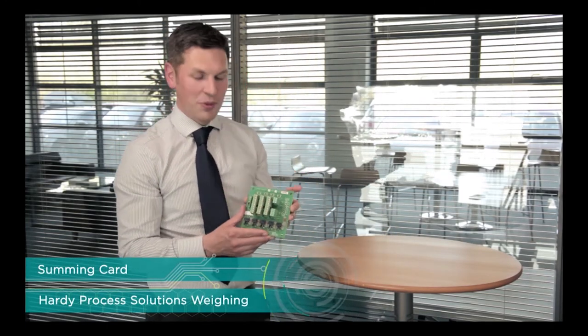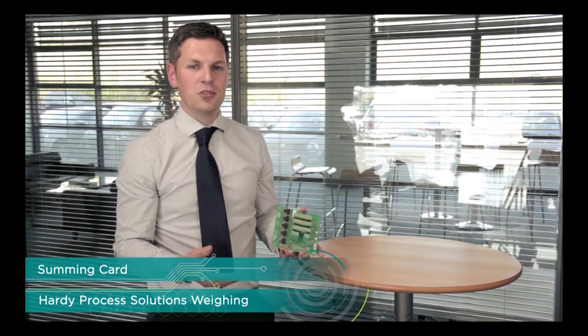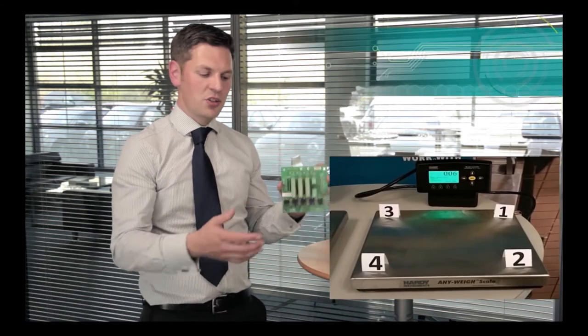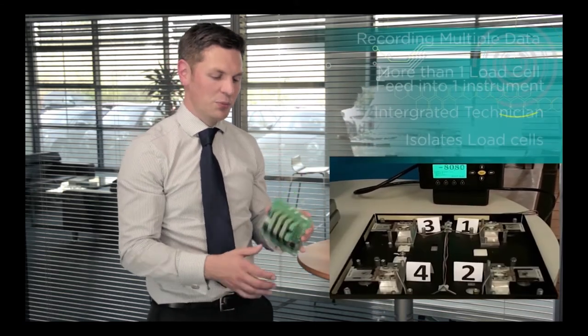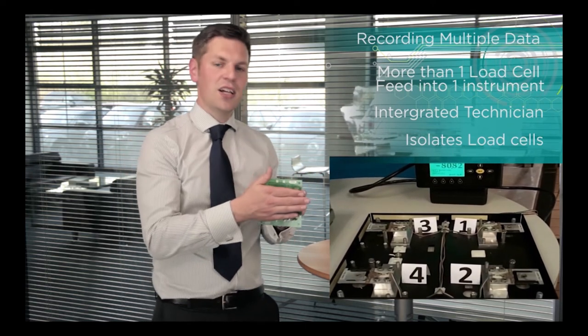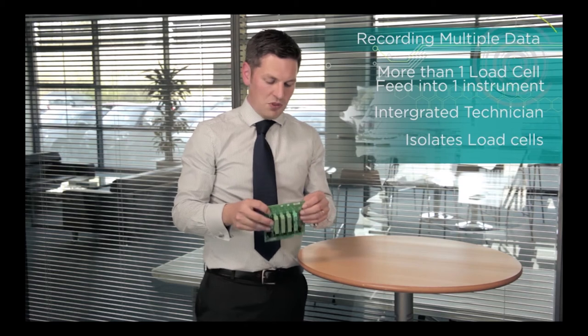This product here is a Summing card. Hardy make a range of these and they're generally used where you've got more than one load cell fed into the same instrument. You might have that if you're recording weights from a vessel or a tank that's got three or four legs on it with a load cell on each of those. You feed that into this and then that would go off to the instrument afterwards.